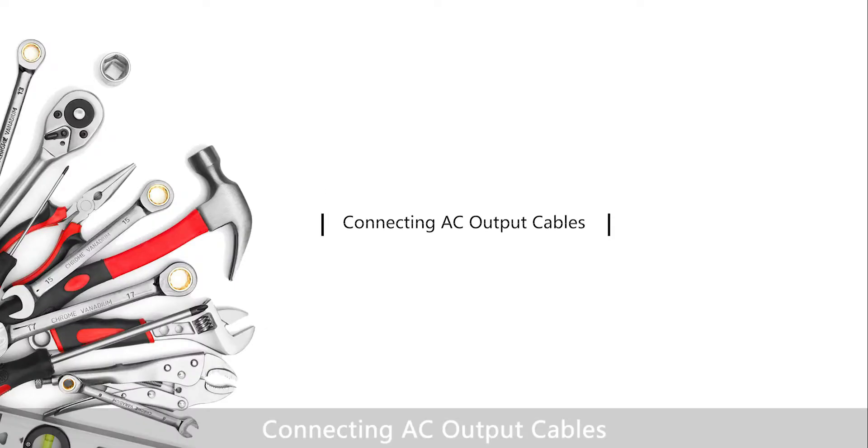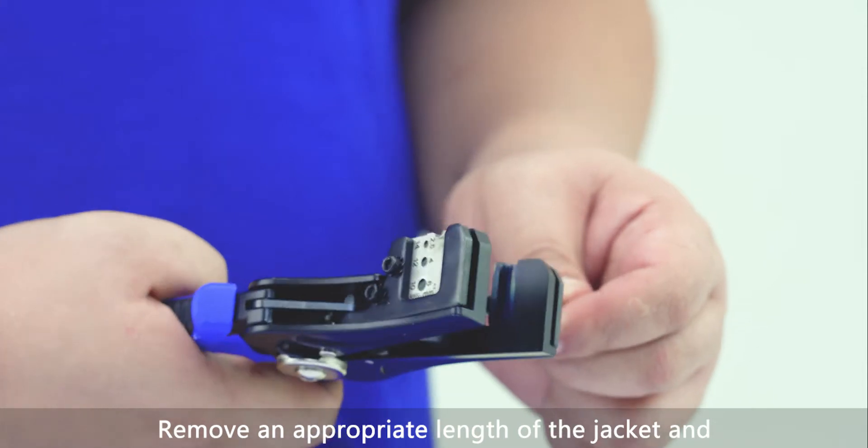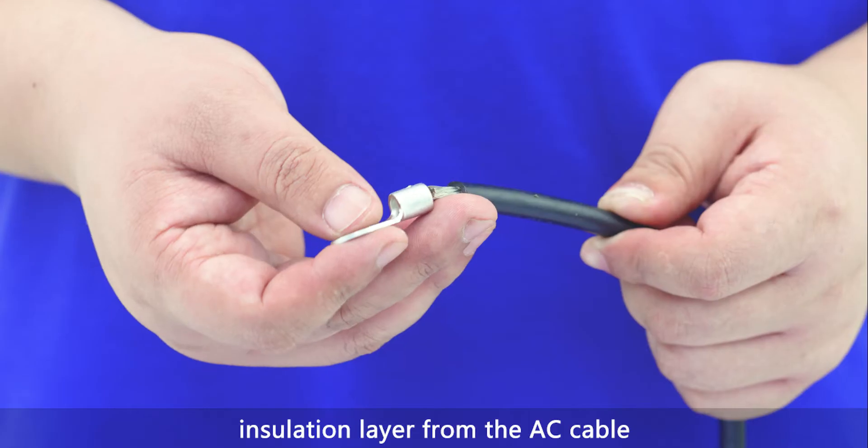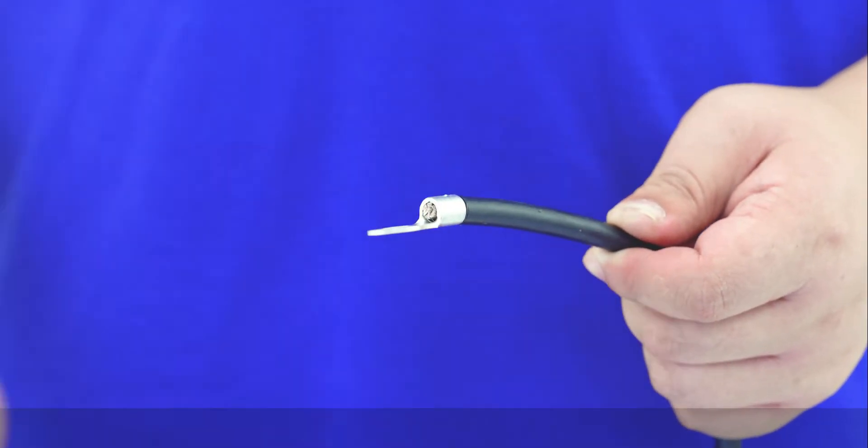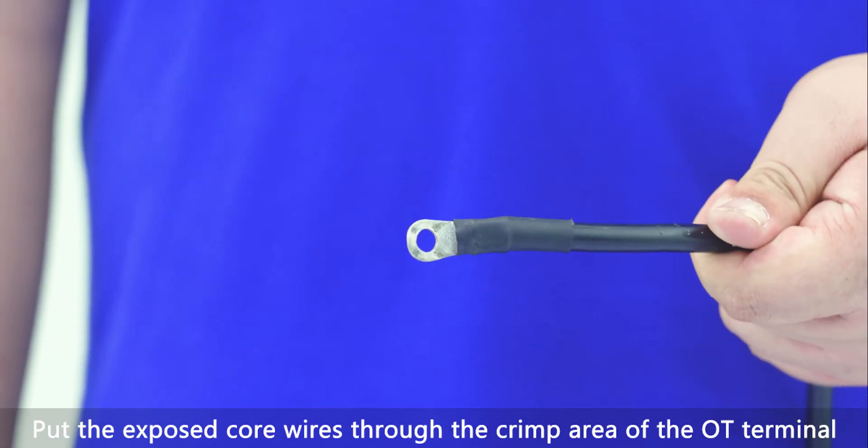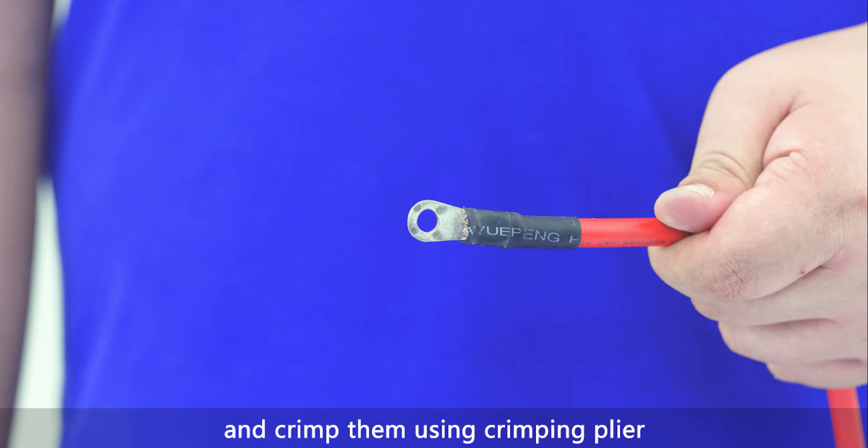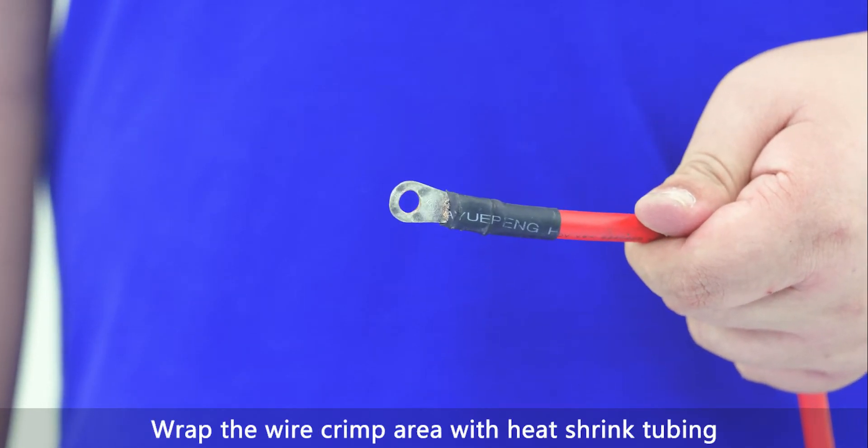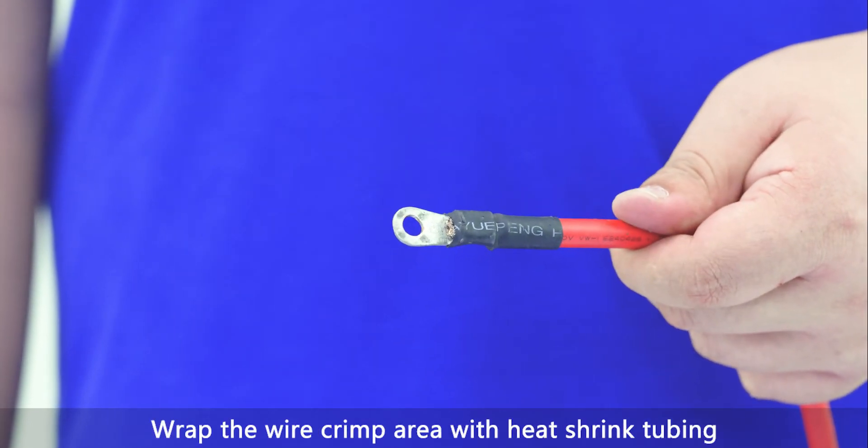Connecting AC output cables. Remove an appropriate length of the jacket and insulation layer from the AC cable. Put the exposed core wires through the crimp area of the OT terminal and crimp them using crimping plier. Wrap the wire crimp area with heat shrink tubing.